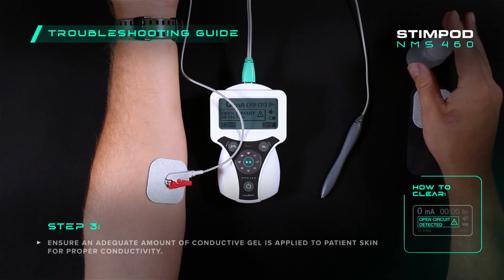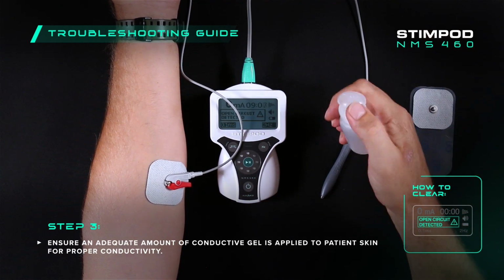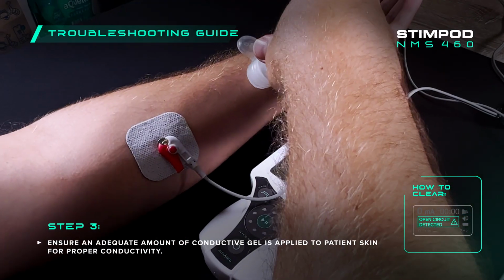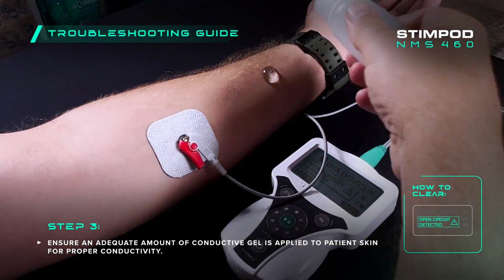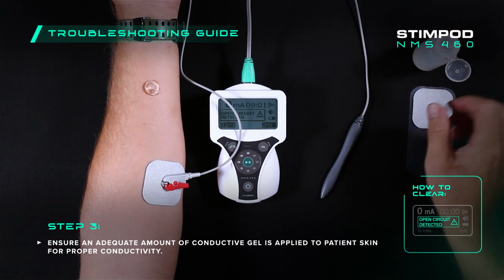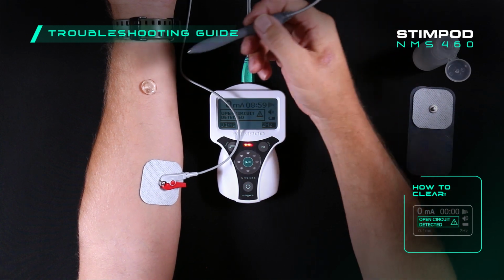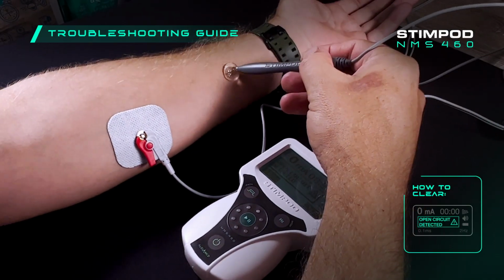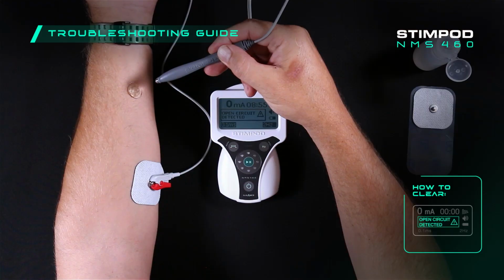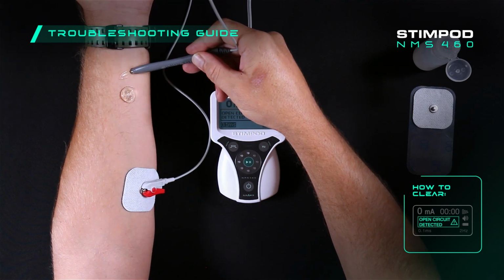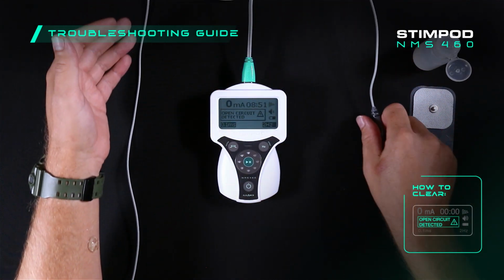3. Ensure there is a fair amount of conductive gel on the area where the probe touches the skin. Some skin may be too dry, which means you will have to use extra conductive gel. If the open circuit detected message is still displayed, this would mean that either your electrode or treatment cable is faulty. You can test each of these as follows.